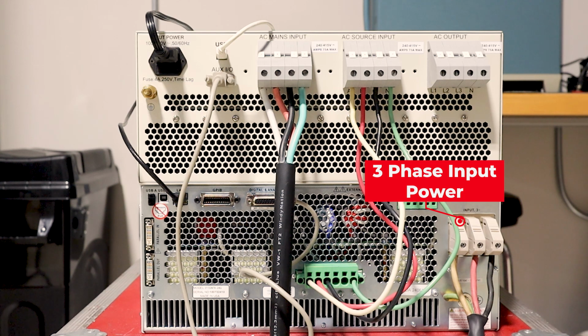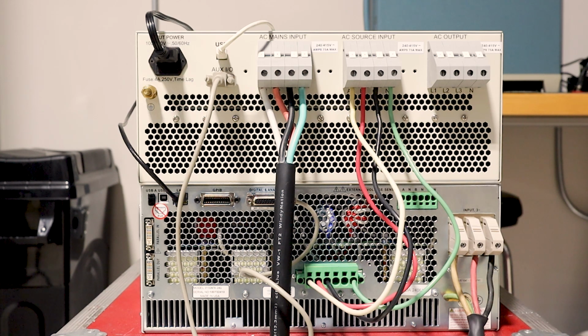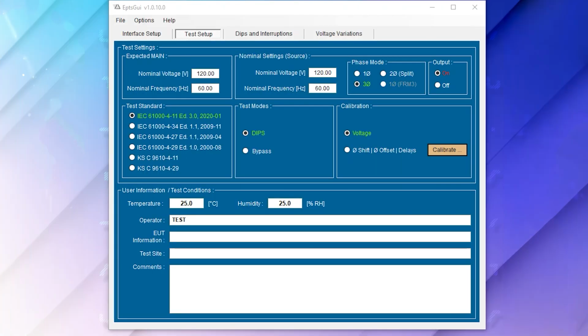To go over the connections briefly, we have two three-phase power inputs from the facility going to the AFX and EPTS, as well as an additional single-phase connection to the input power on the switch. Let's spend some time on the software and running the test. Here's the test setup tab on the EPTS GUI. There's some criteria that needs to be verified and potentially changed anytime the mains connection or AC source is changed. For our rental customers, this will be when the equipment arrives.